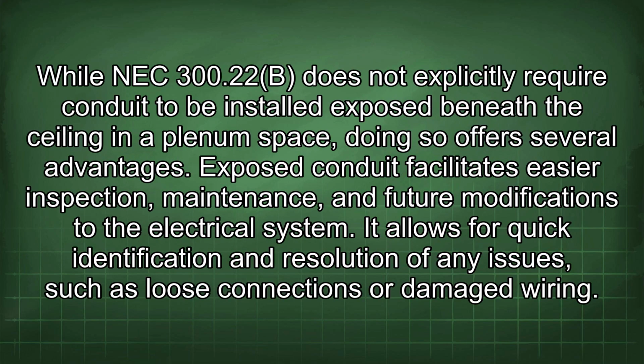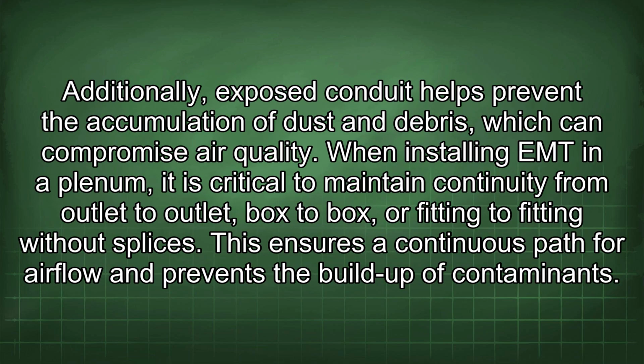While NEC 300.22(B) does not explicitly require conduit to be installed exposed beneath the ceiling in a plenum space, doing so offers several advantages. Exposed conduit facilitates easier inspection, maintenance, and future modifications to the electrical system. It allows for quick identification and resolution of any issues such as loose connections or damaged wiring. Additionally, exposed conduit helps prevent the accumulation of dust and debris, which can compromise air quality.